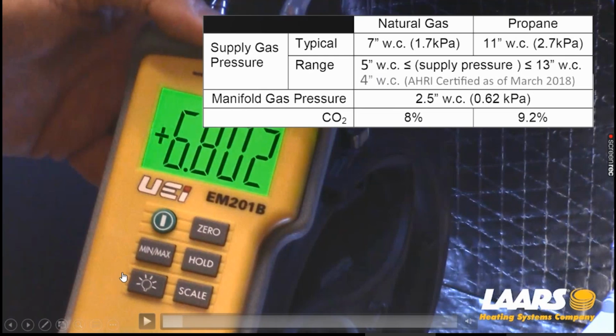Also, low gas pressure switches, keep in mind, you don't want to turn those down too low. We've had cases where maintenance personnel got sick of having to go in when it was in high demand, and it would go into ignition lockout, low gas pressure switch. So he took the cover off and turned that down to 2 inches. Well, if your gas pressure never drops below 2 inches, it won't trip the low gas pressure switch.